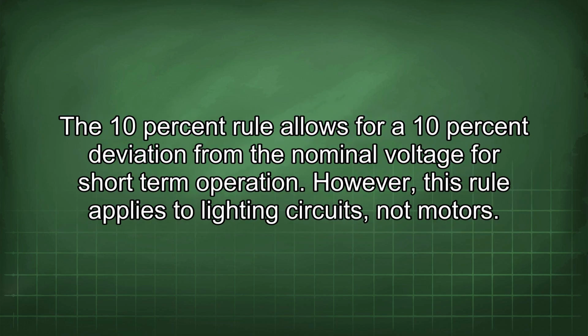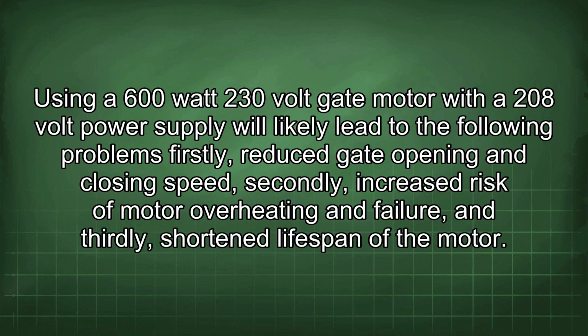The 10% rule allows for a 10% deviation from the nominal voltage for short-term operation. However, this rule applies to lighting circuits, not motors. Using a 600-watt 230-volt gate motor with a 208-volt power supply will likely lead to the following problems. Firstly, reduced gate opening and closing speed. Secondly, increased risk of motor overheating and failure. And thirdly, shortened lifespan of the motor.